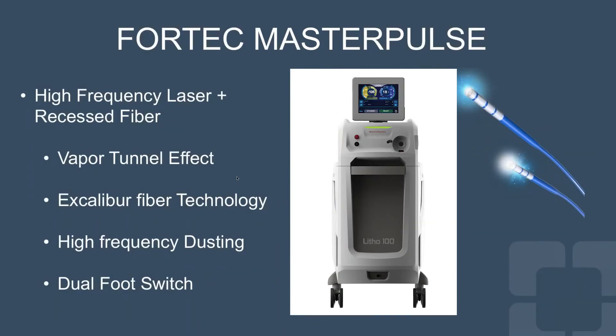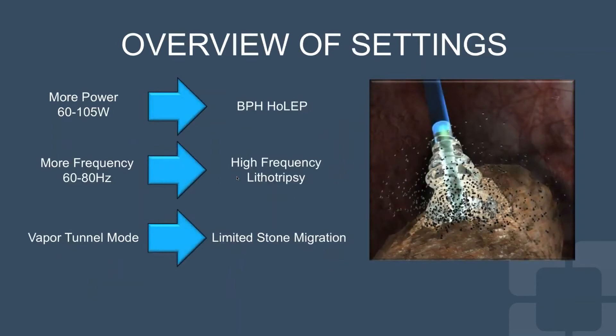Fortec now has the MasterPulse system, which uses a proprietary technology known as vapor tunnel. This is also a high-frequency laser that uses a recessed fiber, and its main feature is the vapor tunnel effect, enabling high-frequency dusting. The machine allows high power ranging from 60 to 105 watts, useful for BPH especially with HoLEP. It can generate high frequencies up to 80 hertz for high-frequency lithotripsy, and the vapor tunnel mode, similar to MOSES, controls stone migration while delivering adequate impact.